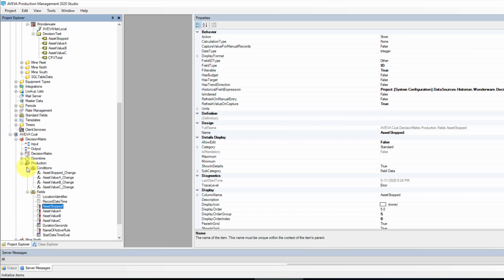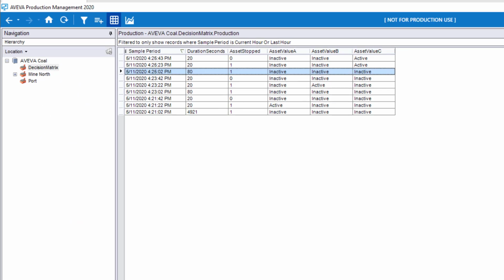And then you also need to set up a capture condition for each of those fields or each of those tags so that if any one tag changes, the production reporting point will capture a new value and it will then show us at what time any one of those changed. Okay, so 4 fields there with the input variables and then 4 capture conditions there. Now that we have that, I'll give you a look at what that looks like inside of the Ampla client.